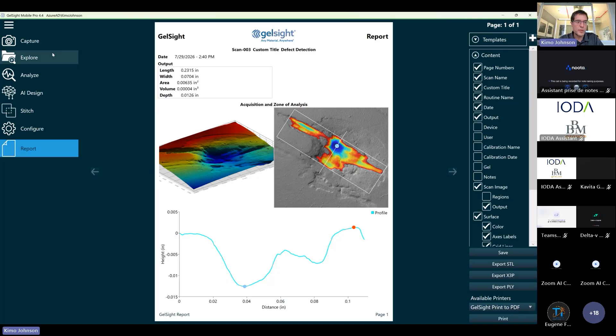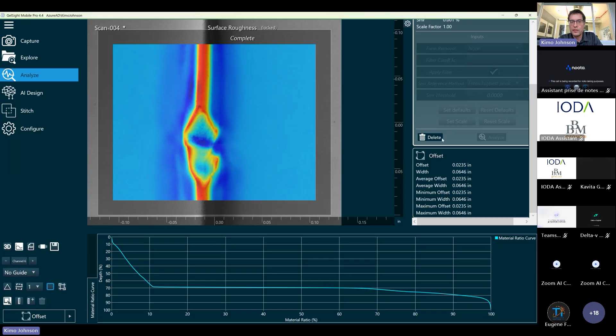Let's say you're inspecting an engine and you see on one of the blades a ding in it. And because we're measuring the deformation of the gel, we have no problems with the leading edge of a blade. Leading edges can be challenging to measure because you have a metallic part that's curved. And so at some point along that curve, you're going to hit the mirror reflection angle, and you'll get dropouts and specular highlights that make the measurement challenging. So for our system, we just, let's get rid of this.